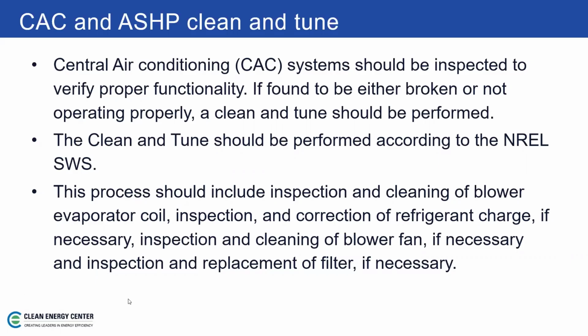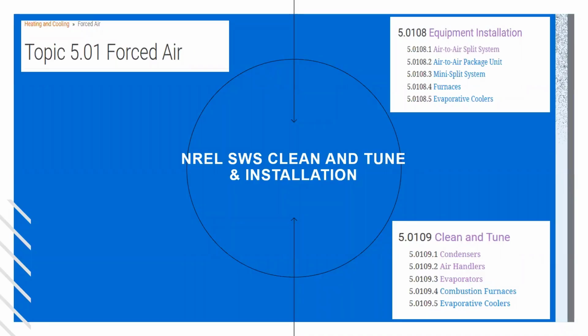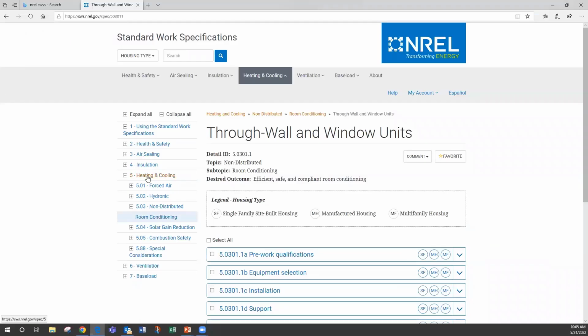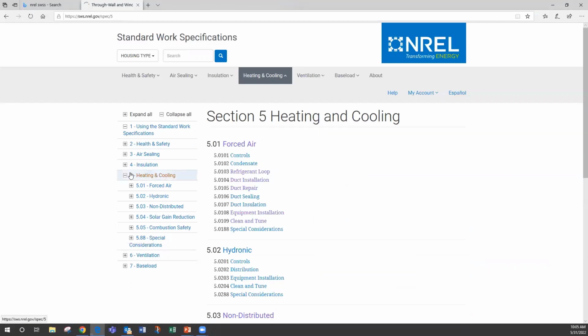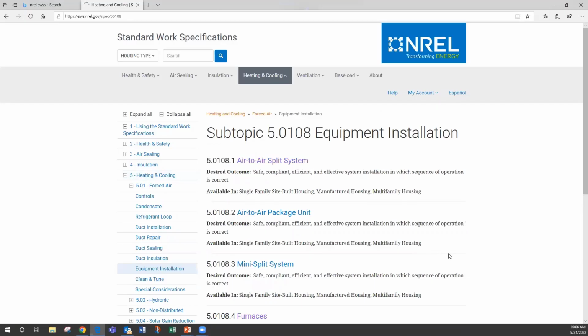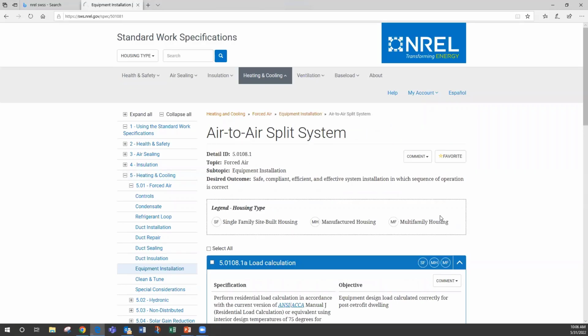And the process should include, at a very minimum, inspection, cleaning of the blower, evaporator coil, inspection and correction of refrigerant charge if necessary, inspection and cleaning of the blower fan if necessary, inspection and replacement of the filter if necessary. So let's go back to the SWS and see what it has to say. And here we're going to be looking at the forced air systems. So let's say, first of all, we want to replace a unit. So if we're going to replace a unit, we should start here with equipment installation, air-to-air heat pump split system.